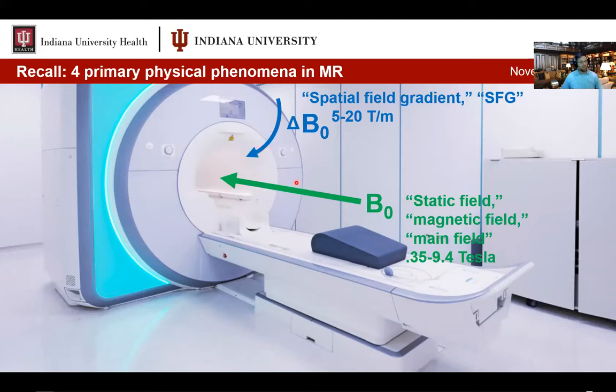So one of the things we often come into conflict with is we find that a certain implant is approved to 7 Tesla per meter spatial field gradient, and we see that there's an 11 Tesla per meter field gradient, you know, up here at this part of the bore. But we feel, well, as long as we keep the patient lower, they'll never get too close to that 11 Tesla per meter spatial field gradient, which is true. They won't get too close to this one, but they might get close to the one down at the bottom, or if they move, they could get close to the ones at the sides. Just remember, this is three-dimensional. The spatial field gradient maximums go all the way around the magnet.